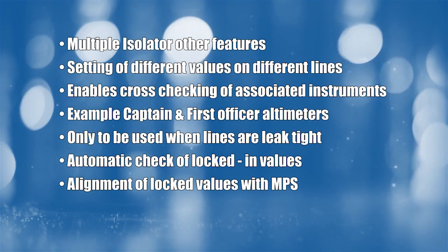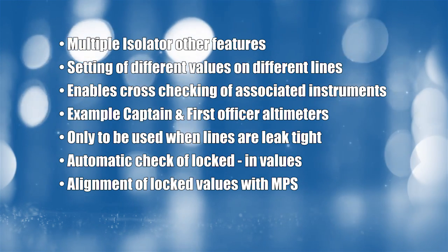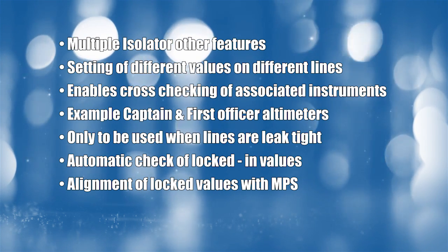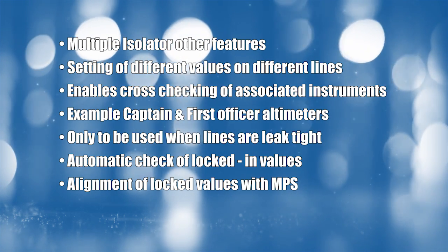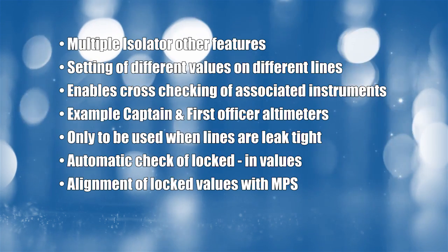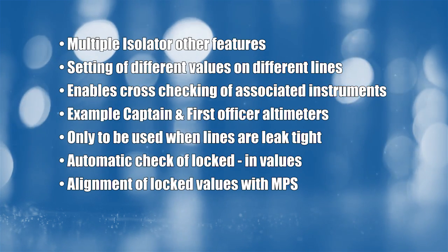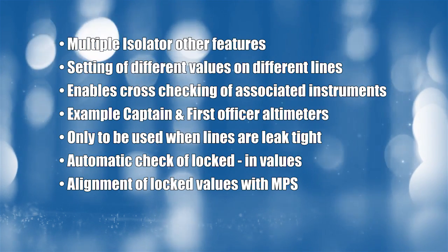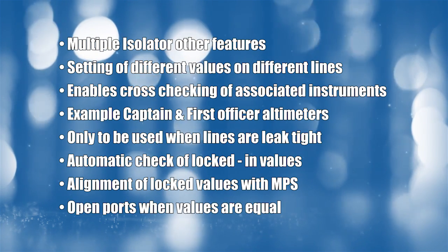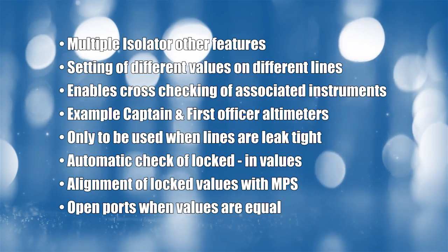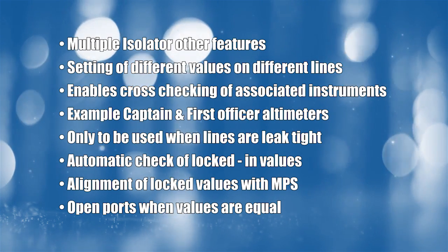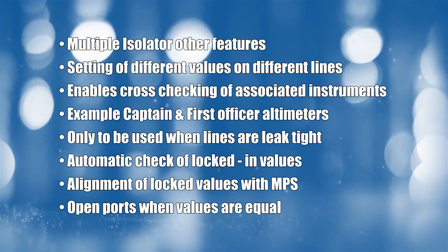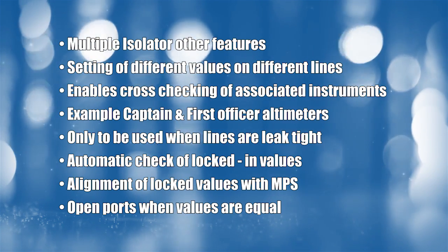If the difference between the current MPS control value and the original locked value is too large, then the MPS automatically changes the MPS controlled value to correspond to the original isolated parameter value before opening the closed port. This ensures that no sudden shock situations that could damage the UUT occur.